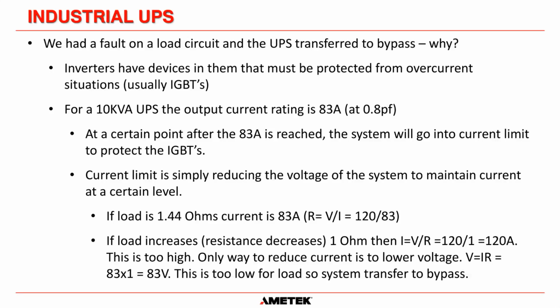And the only way to limit current is simply by reducing the voltage of the system to maintain a current at a certain level. And it's all down to Ohm's law. So the output resistance of the system, if we have 83 amps of current, is 1.44 ohms. Ohm's law says resistance is equal to volts divided by amps. So it's 120 volts divided by 83 amps. That means the resistance of the load must be 1.44 ohms. Now it's important to understand, if the load increases, the resistance decreases. So if we went down to a 1 ohm load, in other words, more load was added, then Ohm's law says we're now going to draw 120 amps. And that's too high.